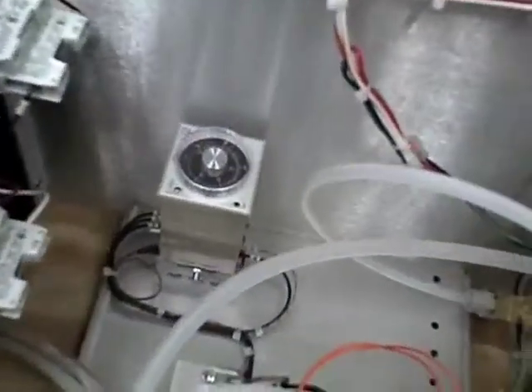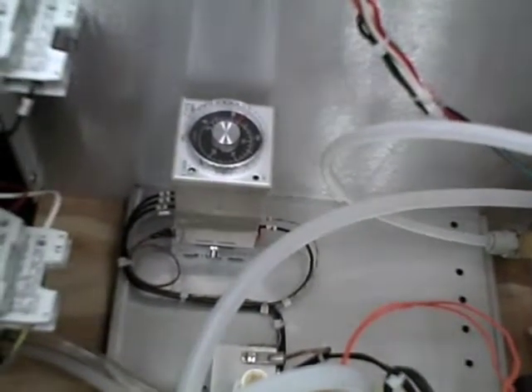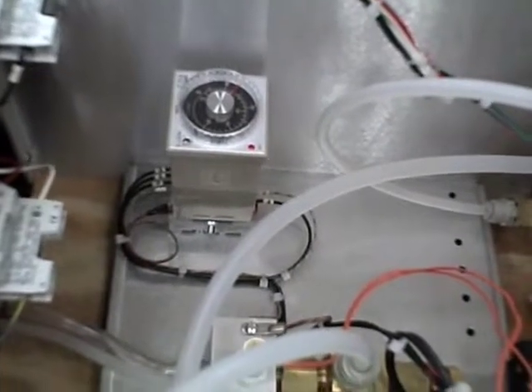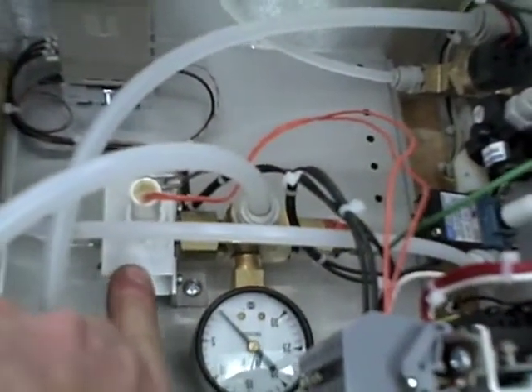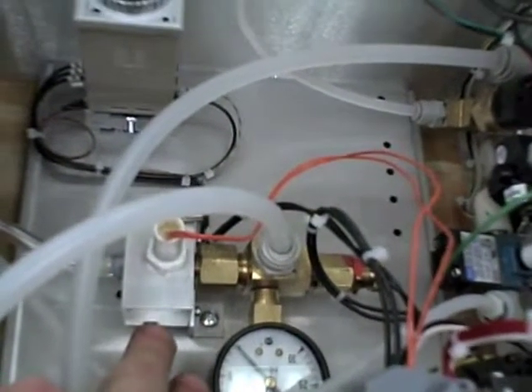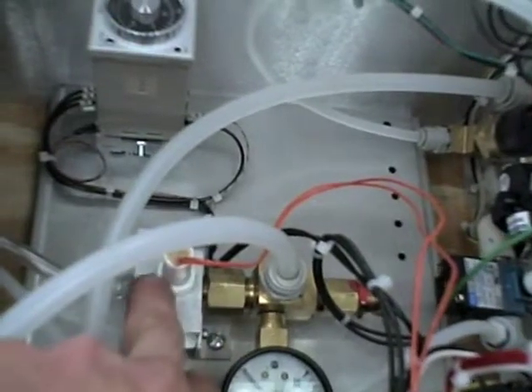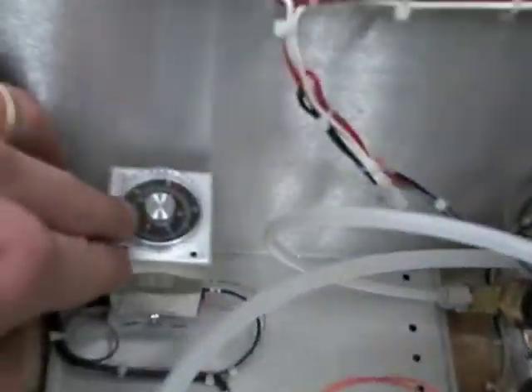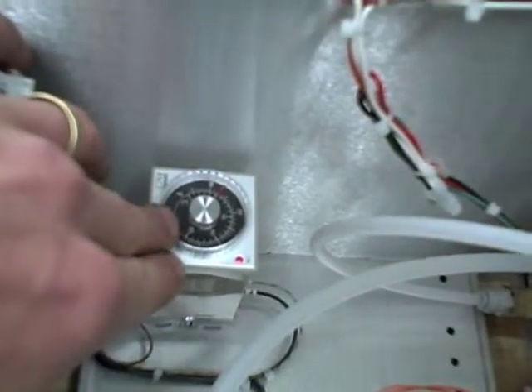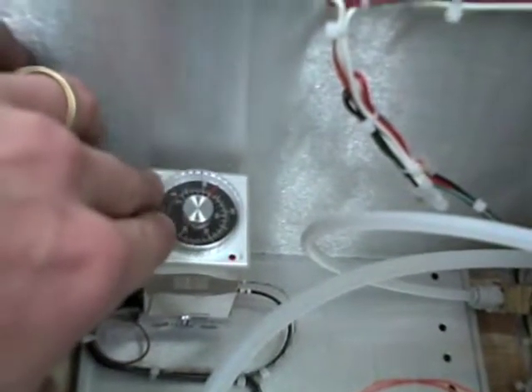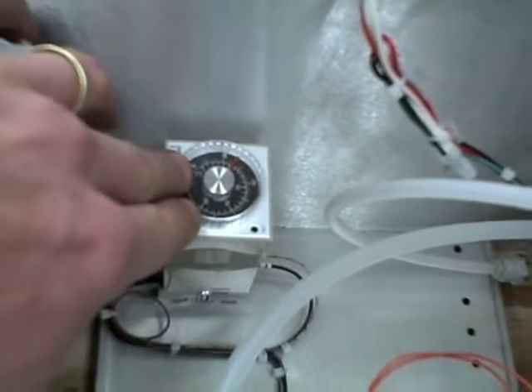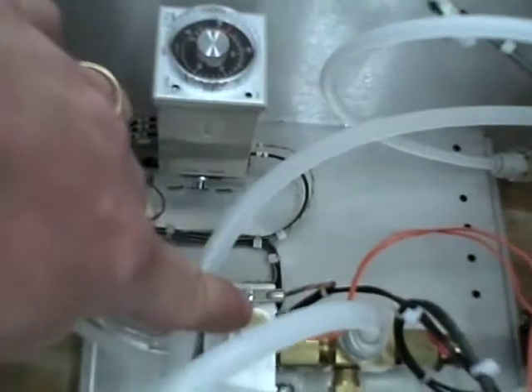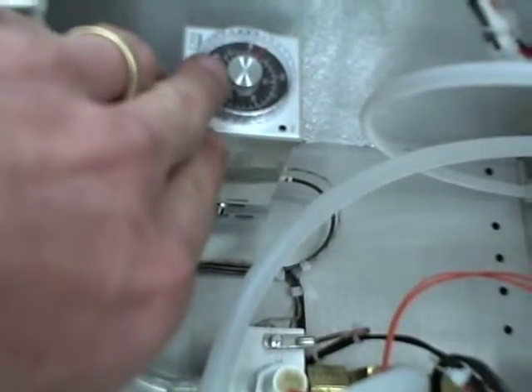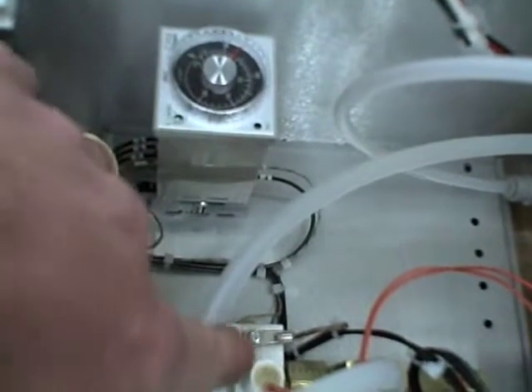We're going to jump back over here again, and a big part of the stability of the machine is in a stable temperature that the sensor is mounted in, and the sensor is mounted in an aluminum block. You can see that right down here, and the block maintains a 130-degree temperature, and the sensor becomes real stable at that temperature, and then this temperature controller controls the temperature of that aluminum block. So we want to keep this right around 130 degrees, and it can be plus or minus a little bit, but as close to 130 as possible. And you actually want to measure the temperature of the aluminum block instead of going just by the reading on the display of the temperature controller, in case that's bad. So actually using a contact type thermometer and pushing it right down on the aluminum and measuring the temperature is best.